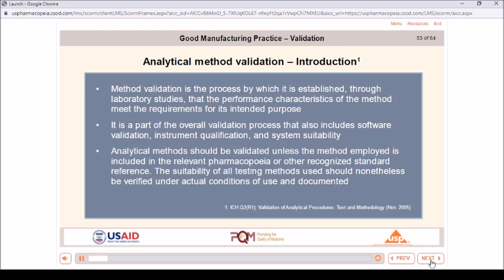Analytical method validation. Introduction. Method validation is the process by which it is established through laboratory studies that the performance characteristics of the method meet the requirements for its intended purpose. It is a part of the overall validation process that also includes software validation, instrument qualification, and system suitability. Analytical methods should be validated unless the method employed is included in the relevant pharmacopoeia or other recognized standard reference. The suitability of all testing methods used should nonetheless be verified under actual conditions of use and documented.